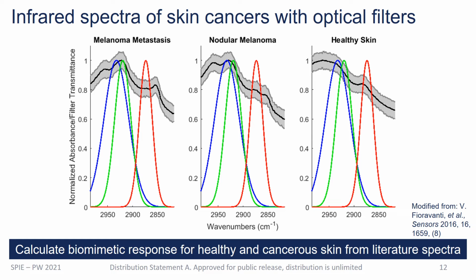We can then use a database of commercially available infrared filters. So we go online and ask, what commercially available filters can we buy? Again, we're not making anything bespoke, to keep the cost low. And we do an exhaustive search over our spectral region of interest using those filters to determine a set that can discriminate between our samples of interest. So this is the filter set which that exhaustive search resulted in. And there's more information about that in the associated preceding article with this presentation.